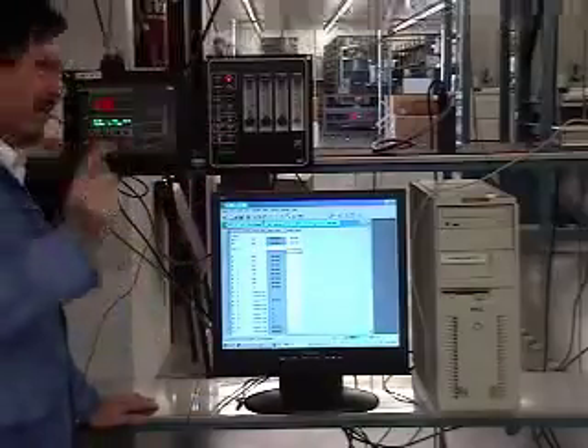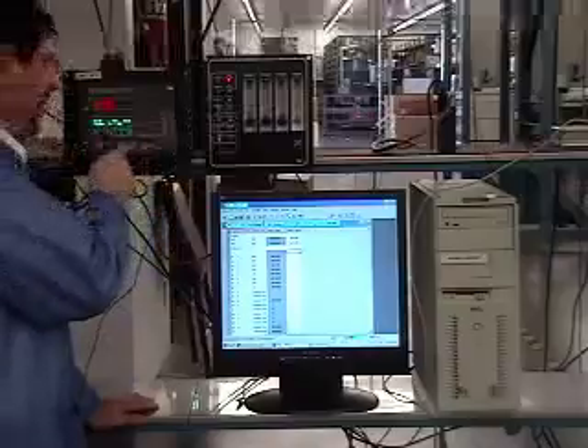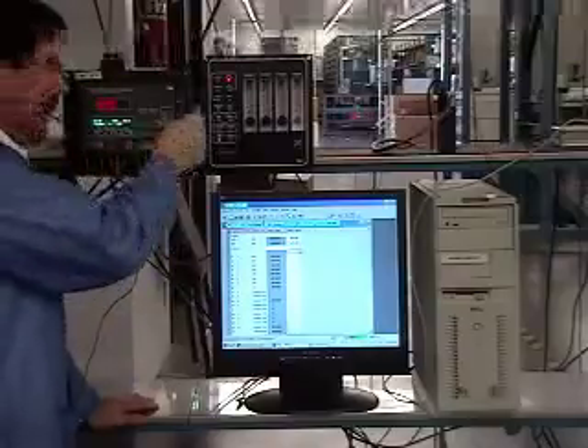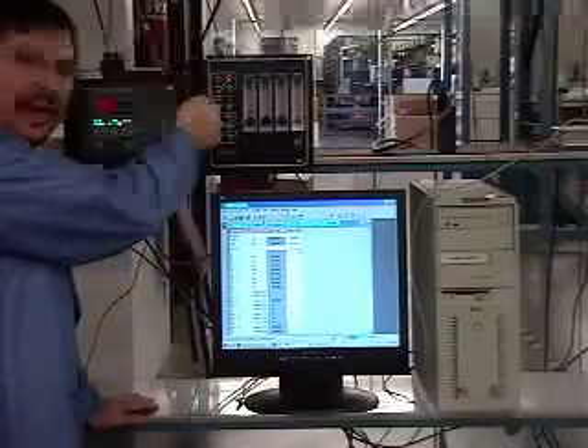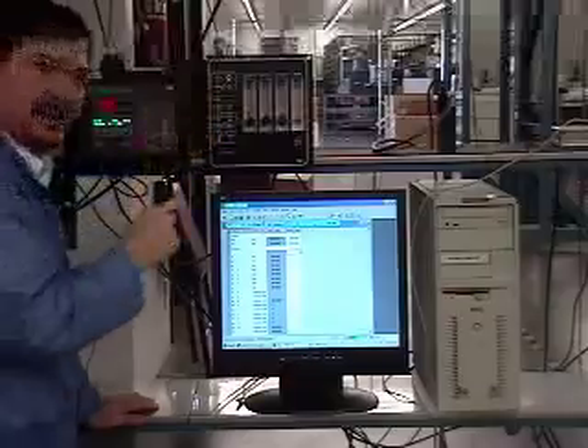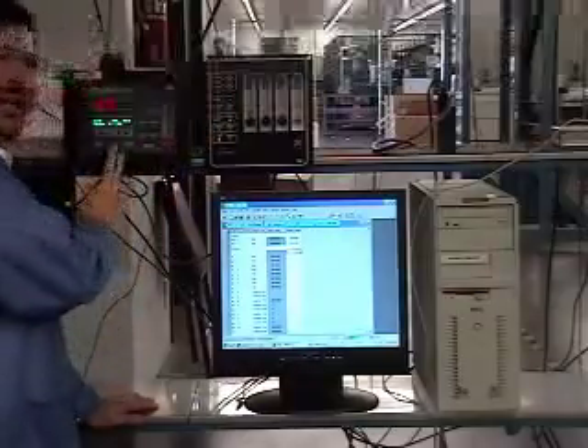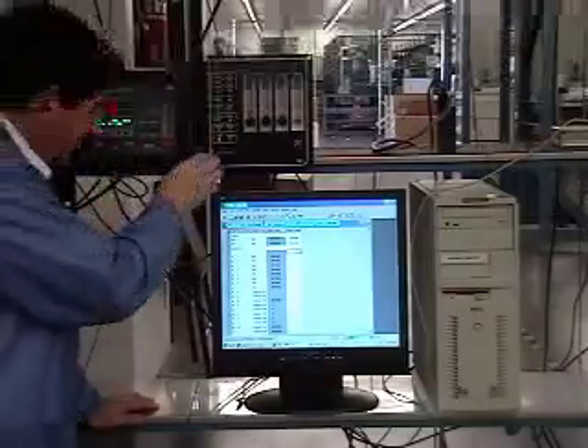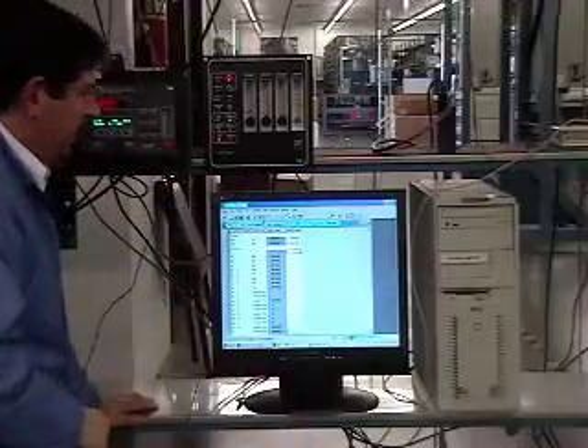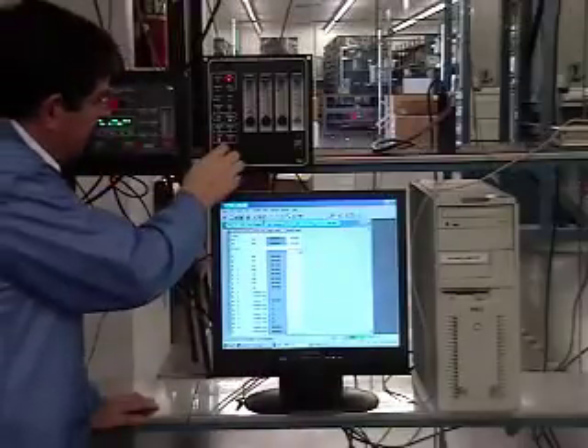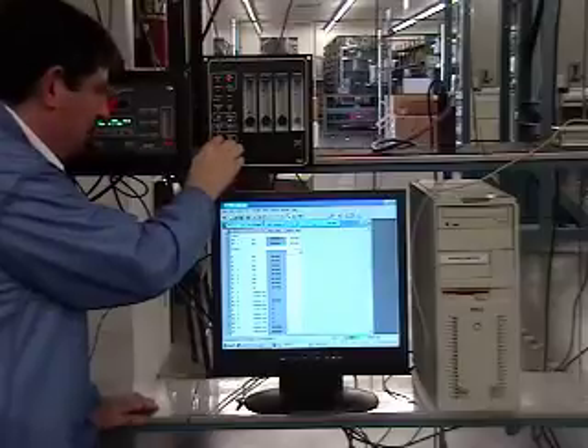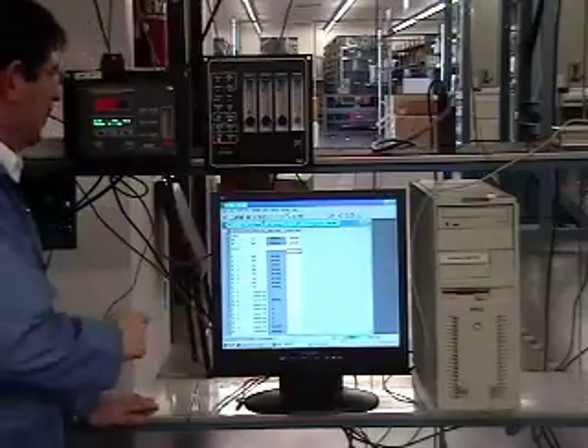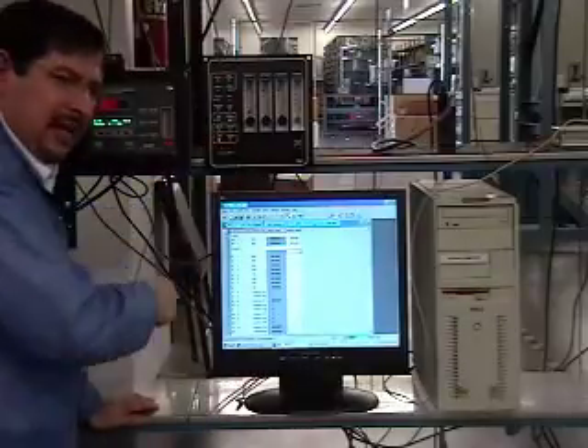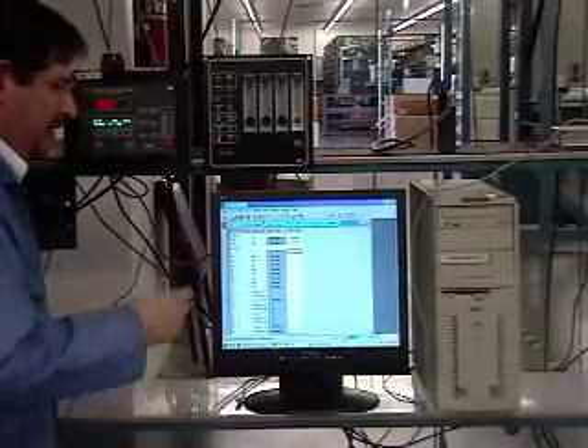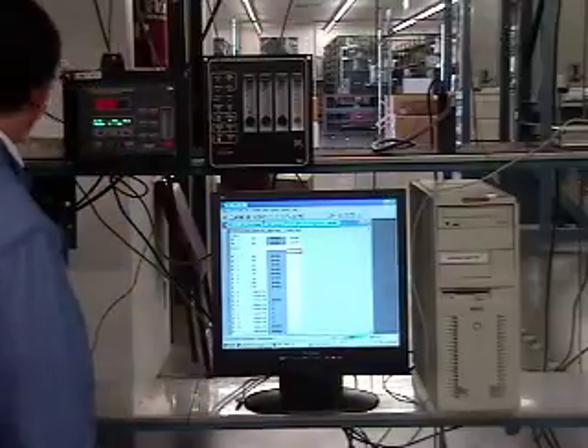Okay, so now, look at that. I send the command, the analyzer is finished spanning. Still, the high calibration gas valve is still open, but it didn't send the analyzer back into span. That's because I still have a signal here. The switch is still up, so I gotta bring it down to switch to another valve if I want. So now, if I move to the next one, I will do a 0, but I wanna first make sure that this is really close to 0.